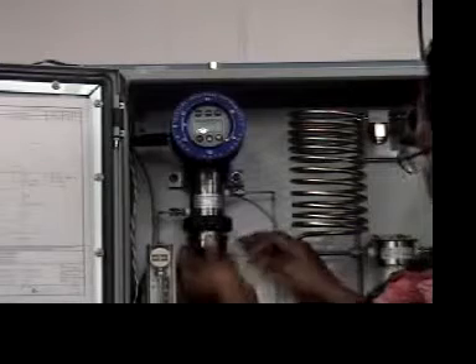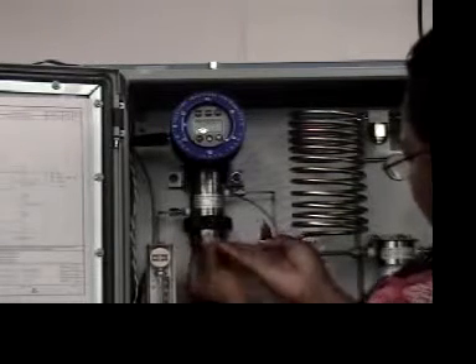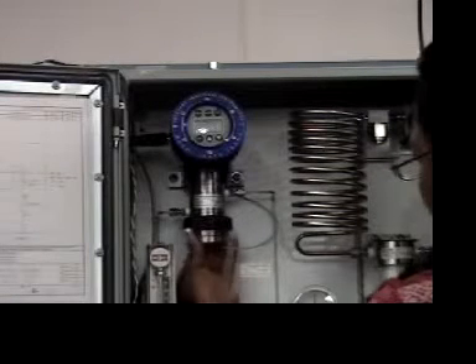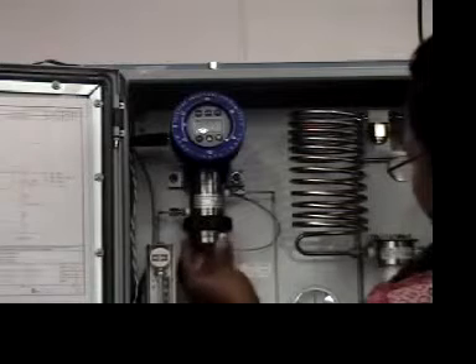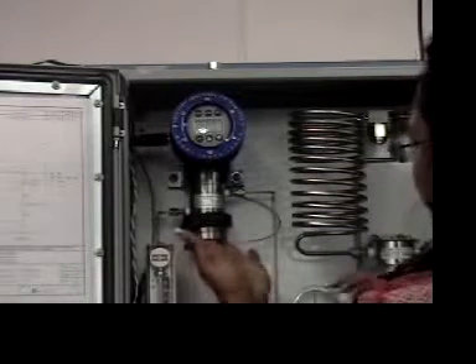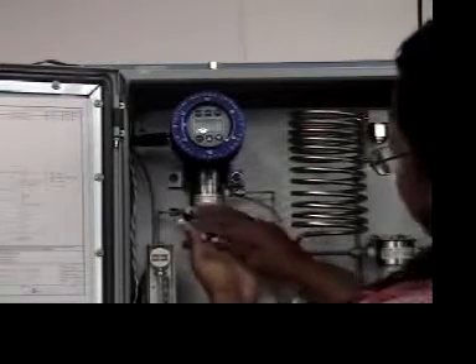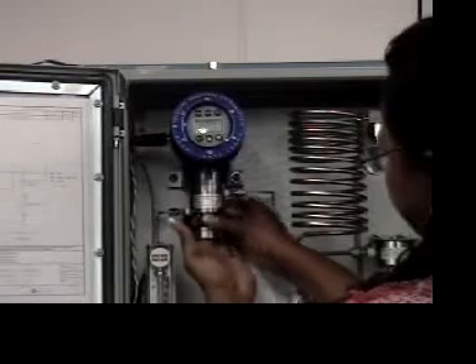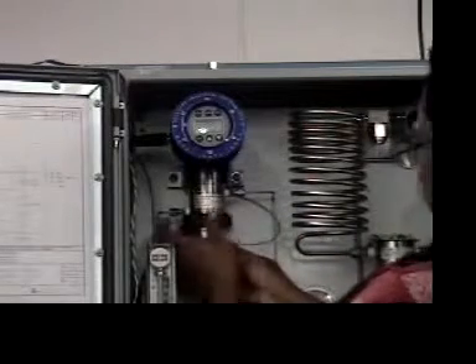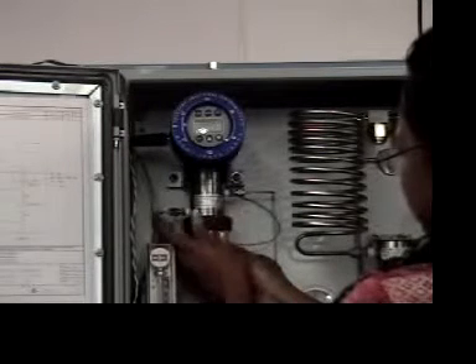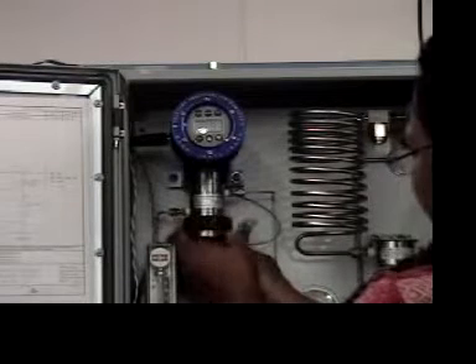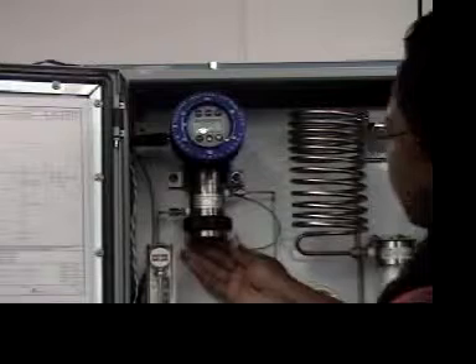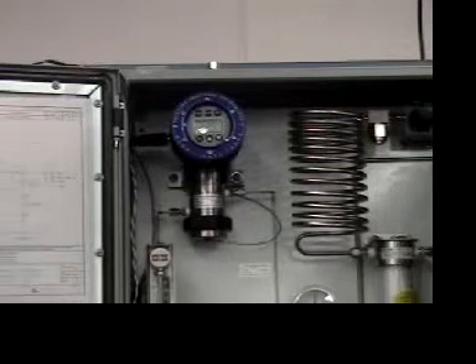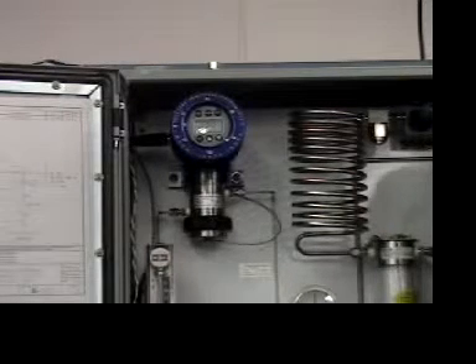There is a little hole on the bottom of this that locks into a pin in the bottom, and you'll feel it. You can turn it until you feel the little hole catch. There you go. Alright, the pin and the hole are aligned, and go ahead and turn the ring the opposite direction, which is now clockwise, and close the cell holder. Now the sensor is installed, and you just want to give it a few minutes, maybe about 20 minutes if you're just installing a new sensor, for the sensor to become stabilized before you can start doing a calibration of this unit.